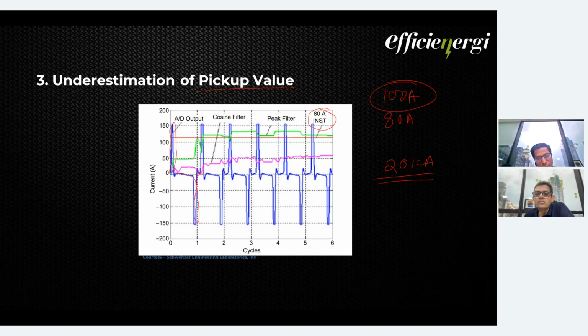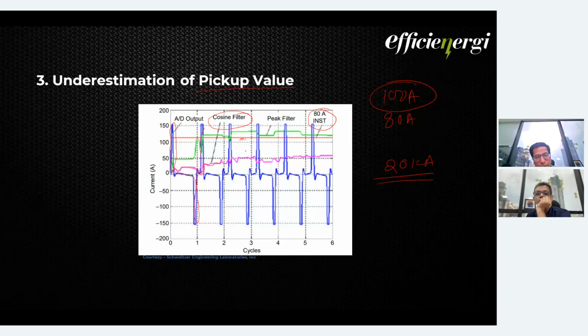So it is kind of showing this kind of waveforms on your DRs, disturbance recorders. Okay, so if you see the saturation level and the measurement after the cosine filter, because every relay has cosine filters just to filter out the unwanted harmonics. So this pink line is actually read by the relay. So this pink line is very well below the pickup. So even if there is a fault on the secondary, just because your CT is heavily saturated, this relay will not at all pick up, because it will not reach the pickup value at all.